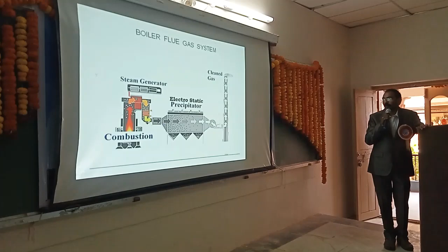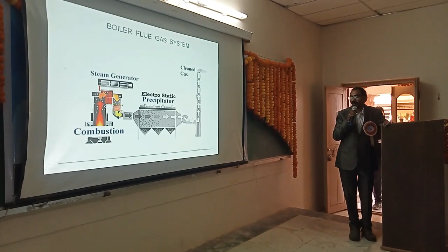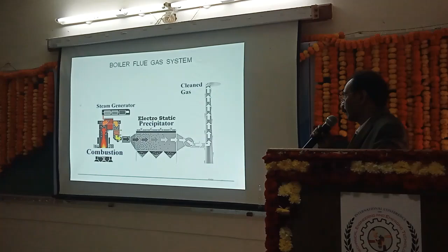Next slide, sir. Here you can see the combustion. Then the flue gas goes to the electrostatic precipitator, because the flue gas contains ash that will be cleaned before it is emitted to the atmosphere. When the flue gas passes through the ESP, there will be an anode and cathode. The solid particles will be ionized, and the ionized particles will be attracted to the collectors. Thereby dust particles will be collected. The clean air goes to the chimney.